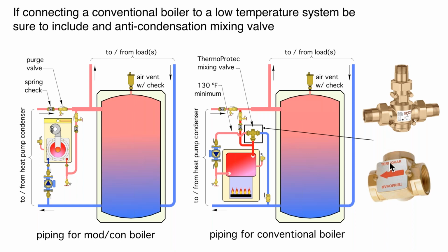There's a couple valves on the market. Basically, these are just high flow capacity thermostatic valves, and they can take this cool water coming back and they'll actually blend it with some of the hot water coming out of the boiler so that the return water typically stays above about 130 degrees Fahrenheit. And that's a serious issue. I've seen systems where this kind of detailing wasn't done, and you can destroy that boiler in a matter of months due to sustained flue gas condensation. You can also create rust right through the vent connector pipe. So it's a safety issue. I just want to bring it up in the case where you're retrofitting a system with what we call a conventional boiler.